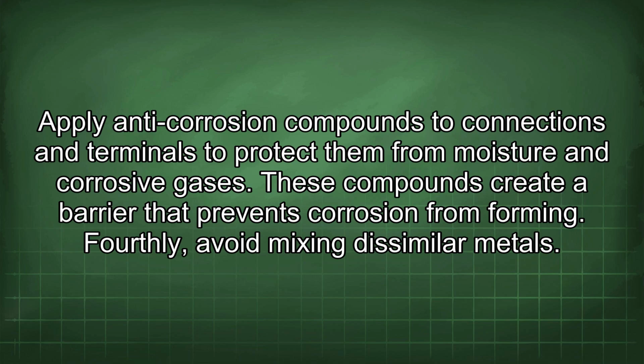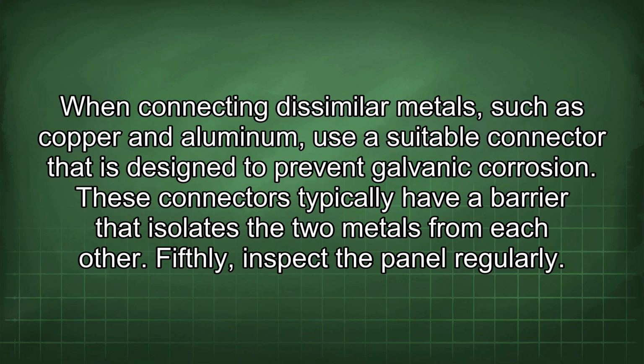Fourthly, avoid mixing dissimilar metals. When connecting dissimilar metals, such as copper and aluminum, use a suitable connector that is designed to prevent galvanic corrosion. These connectors typically have a barrier that isolates the two metals from each other.